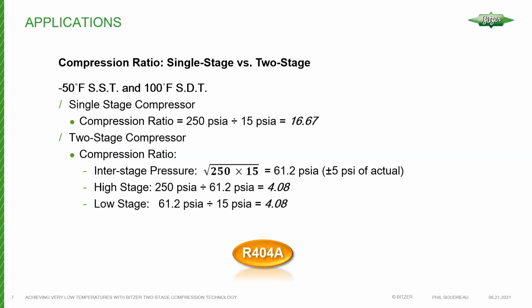If we were to break down each stage of the compressor, in the high stage we still have the same discharge pressure of 250 PSIA, but its suction pressure is essentially the interstage pressure, which is 61.2. So we divide the 61.2 into the 250 and we get a compression ratio of 4.08. In the low stage, it's similar. The interstage is actually the discharge for the low stage. 61.2 divided by 15 PSIA results in 4.08.